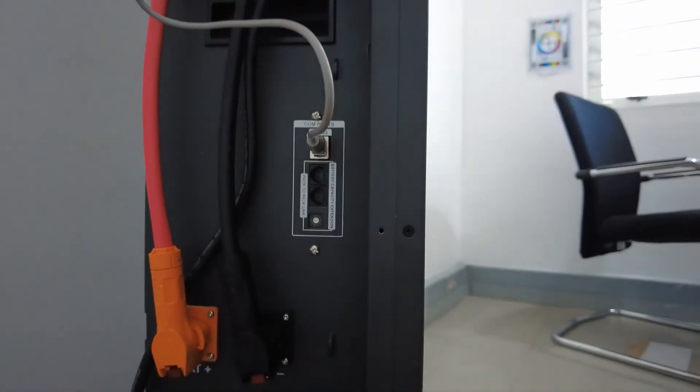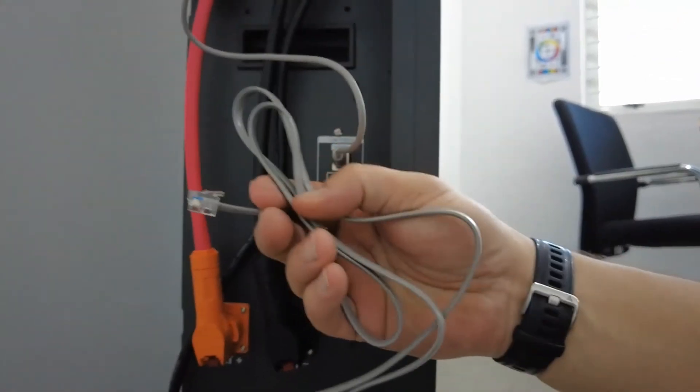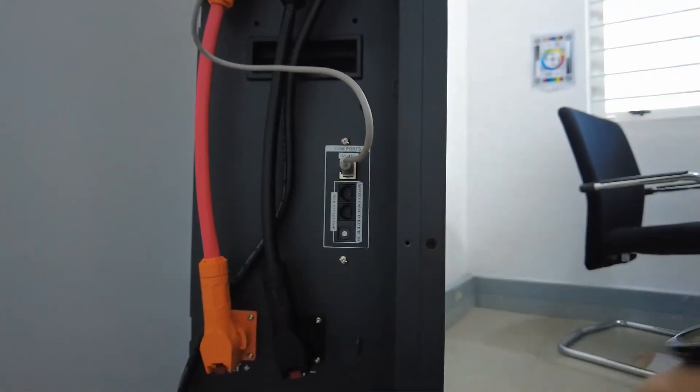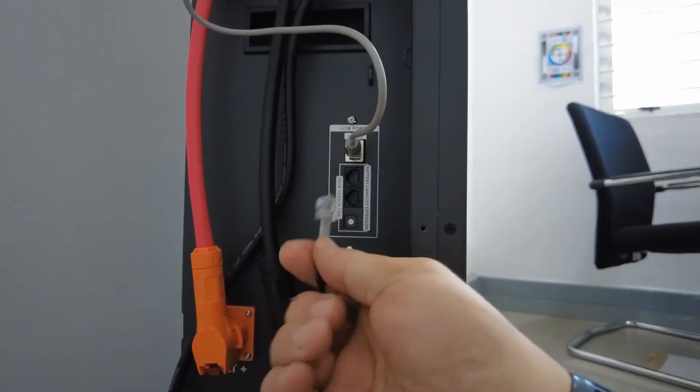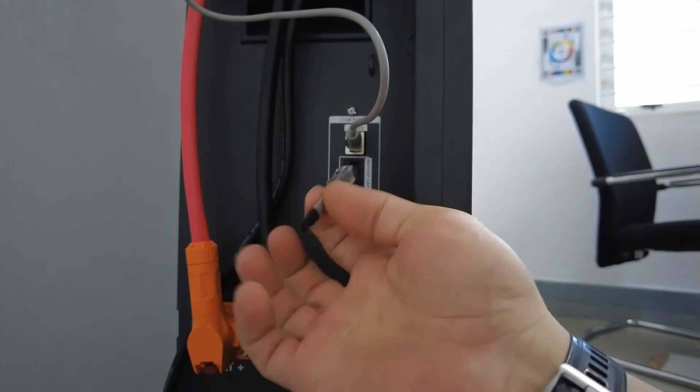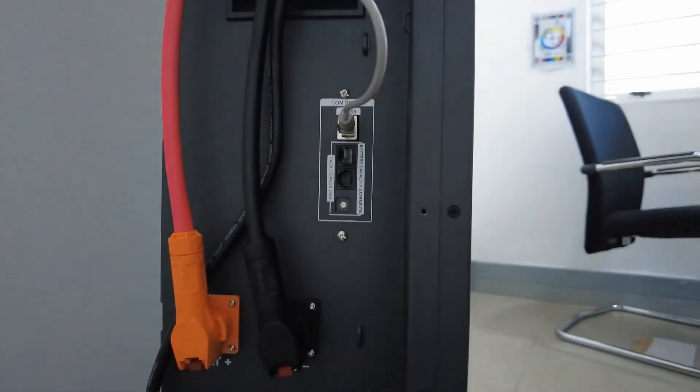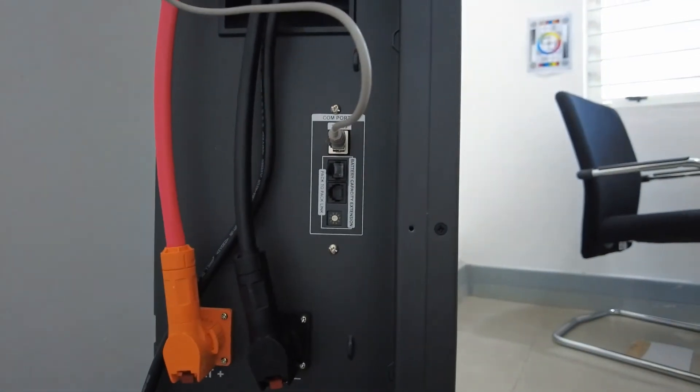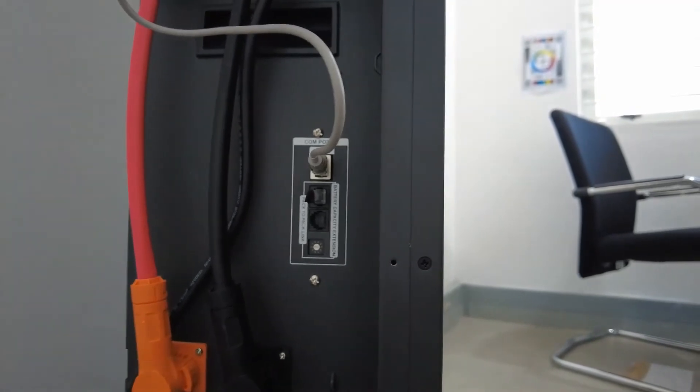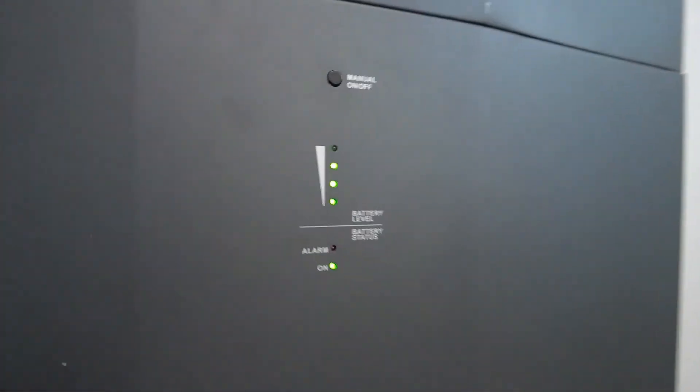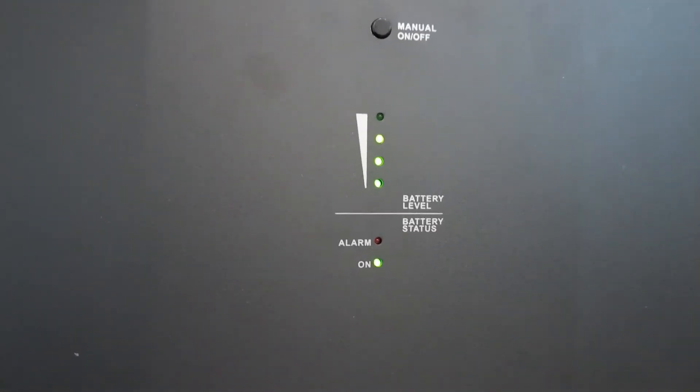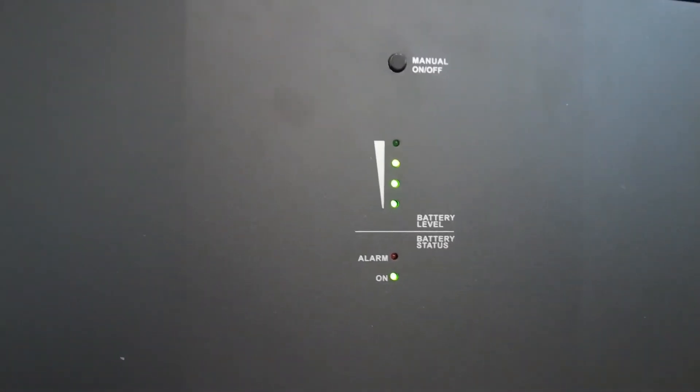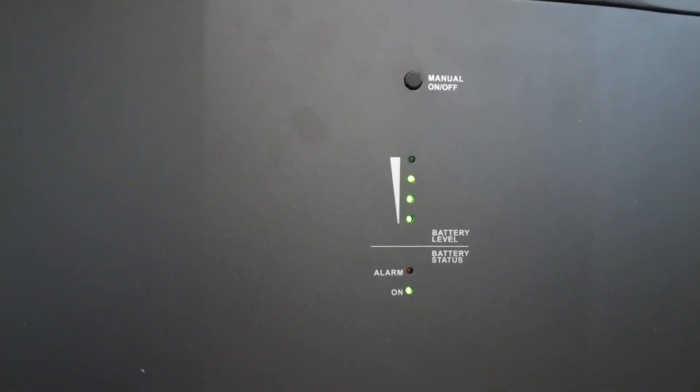Just keep on daisy chaining it using this alarm cable until you reach the last battery, and your last battery will then get this connection communications cable. Just connect that into your first top port, and then immediately you can see the alarm light has cleared. It's not flashing anymore.